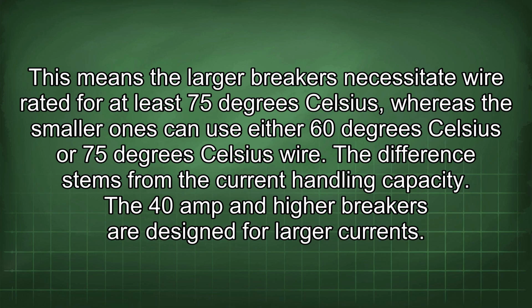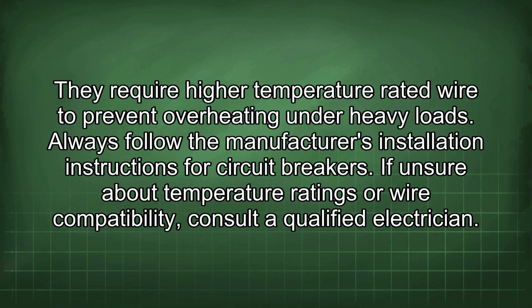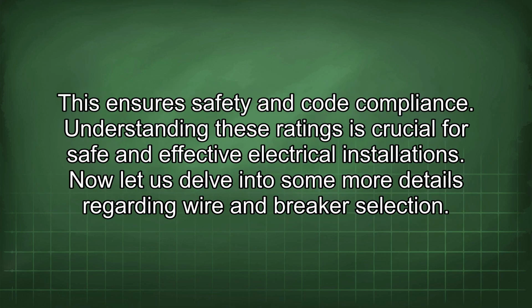The difference stems from the current handling capacity. The 40 amp and higher breakers are designed for larger currents. They require higher temperature rated wire to prevent overheating under heavy loads. Always follow the manufacturer's installation instructions for circuit breakers. If unsure about temperature ratings or wire compatibility, consult a qualified electrician. This ensures safety and code compliance. Understanding these ratings is crucial for safe and effective electrical installations.